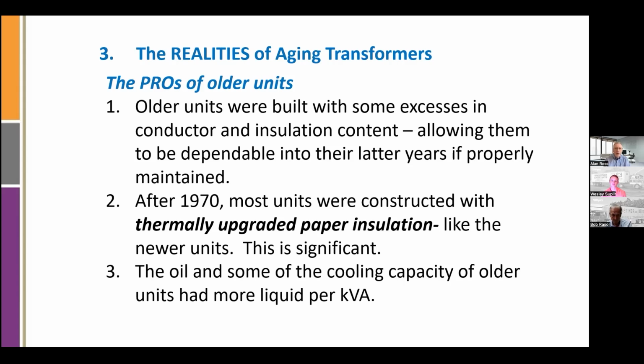But would you agree that transformers today are made differently? They meet the standard, but they're made differently than they were back in the 70s and 80s? With computer design, the liquid percentage drops. The gallons per kVA are down lower, better designs. This is dovetailing right into these next couple comments here. And in the 1970s, thermally upgraded insulating paper made a difference. This helped aging in some respects.